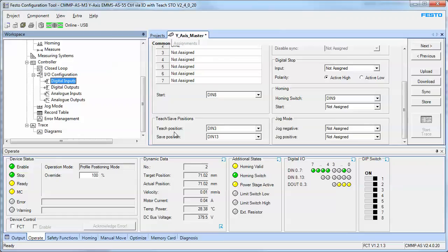If you were to cycle power the controller, the old position value would be there. If you execute the save position, it's moving that volatile memory, the saved data, to the EEPROM so that upon cycle of power, those teach positions have been saved permanently.